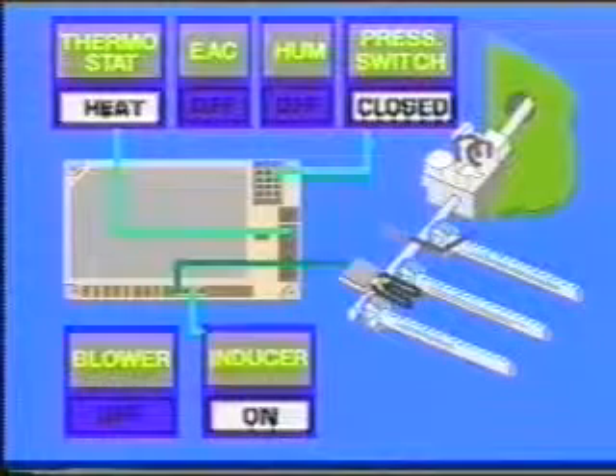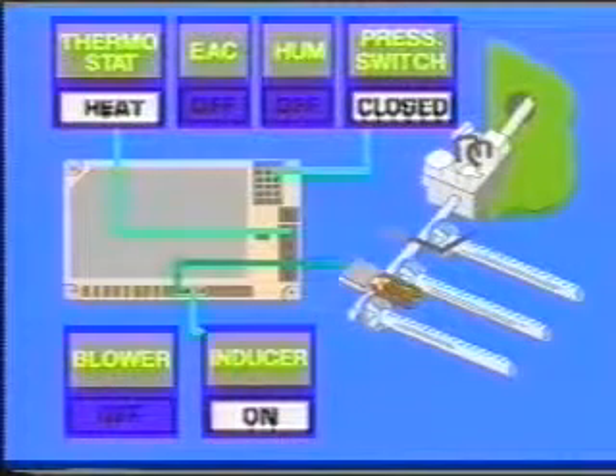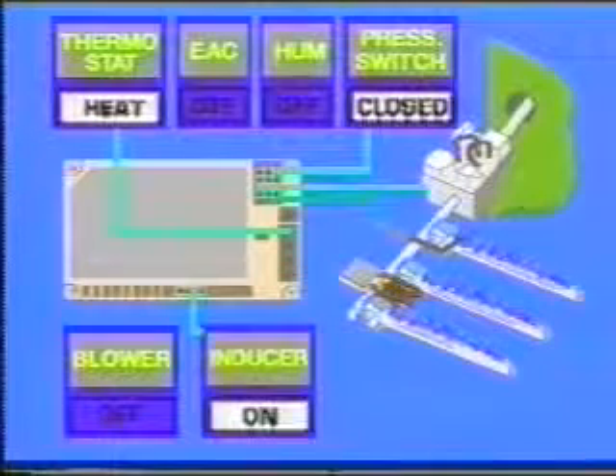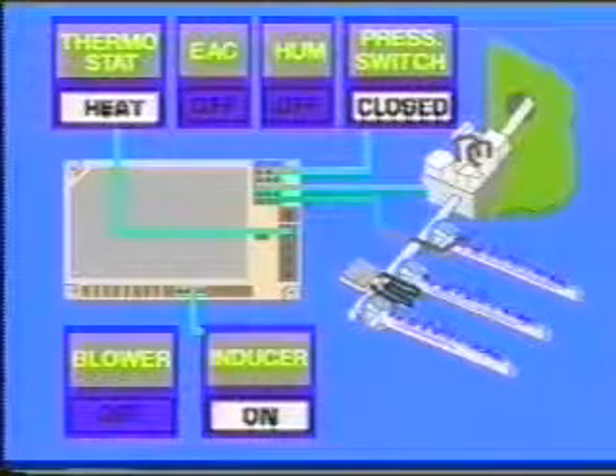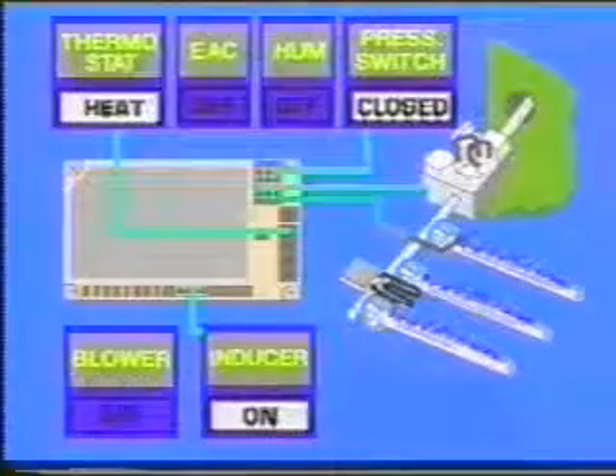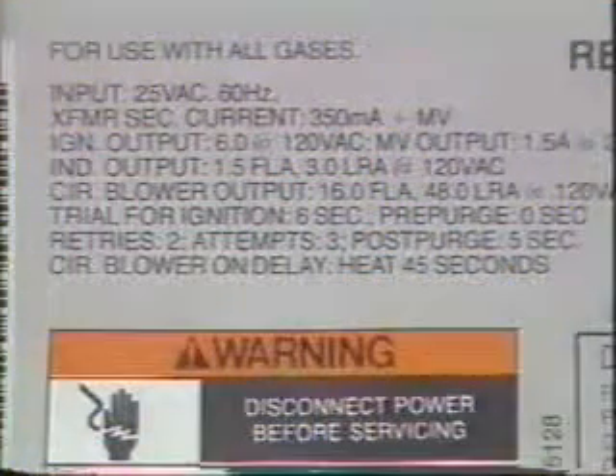The module will continue to call for retries until flame is proven or the module locks out. The number of retries varies from one furnace manufacturer to another. The retry specification, as well as other module characteristics, is specified on the label of each control. The multiple retry for ignition eliminates nuisance lockouts. Any number of factors can cause a flameout during a normal combustion cycle. These include a momentary loss of gas supply, flame blowout, or loss of the flame probe signal.